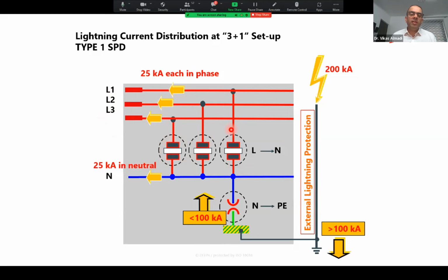When we connect the arrestor between line and earth, there could be a possibility of damage. The solution is we have to use RCBs, ELCB with that kind of arrangement, but nobody uses it. But in the meanwhile, second thing, in India particularly, you asked me from the experience also. If you connect the arrestor between line and earth, because of very high varying voltages between line and earth in a TT system, and naturally it is going to be there, the arresters are bound to fail. The arrestor definitely fails there, and there are instances. I'm not going to say the makes here basically, but there are instances where even the arresters caught fire. So this becomes a very big safety issue if we connect between line to earth. It is always good to connect between line to neutral, so that you have a controlled short circuit whenever there is a failure, so that there is a tripping of the fuse or an MCB to bring it back to the safe line. I hope the first question is answered.